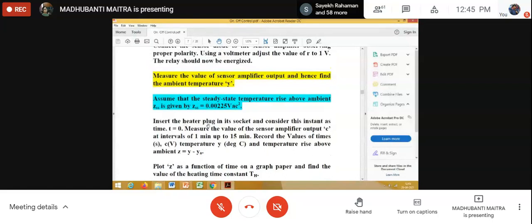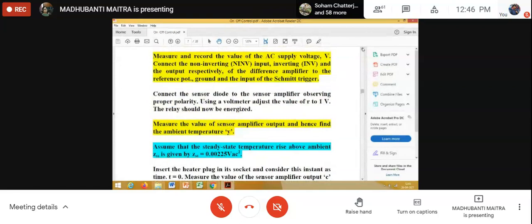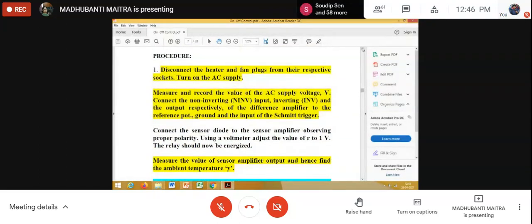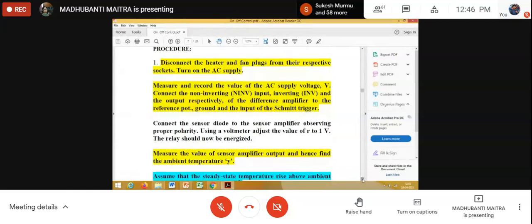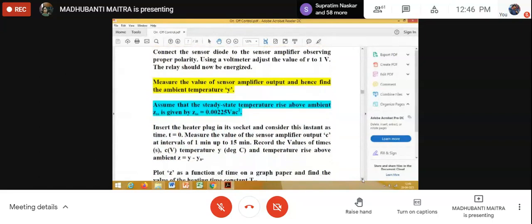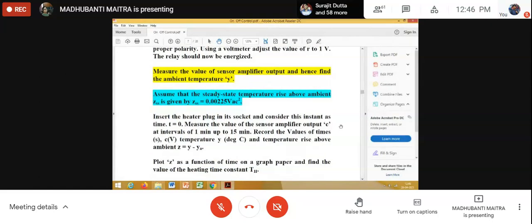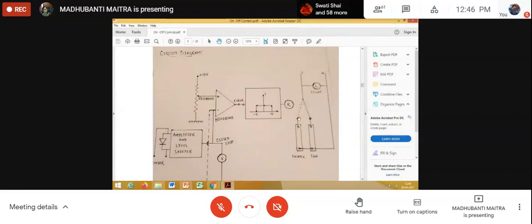So now we'll insert the heater plug in its socket and we'll consider this instant as time t equal to 0, right? And measure the value. Yes, as I said, now R minus C error voltage is positive, so the relay should now be energized. So that LED will glow. That means the relay is energized. Next, we have put the heater plug into its socket, and since the relay is energized, this contact is closed. That means the heater is now connected in the circuit, whereas the fan is cut off. Clear?